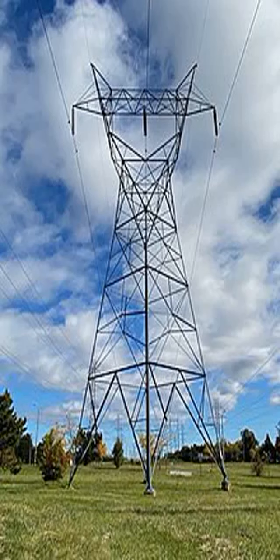For single-pole HVDC transmission with ground return, towers with only one conductor can be used. In many cases, however, the towers are designed for later conversion to a two-pole system. In these cases, often conductors on both sides of the tower are installed for mechanical reasons. Until the second pole is needed, it is either used as electrode line or joined in parallel with the pole in use. In the latter case, the line from the converter station to the earthing electrode is built as underground cable, as overhead line on a separate right-of-way or by using the ground conductors.